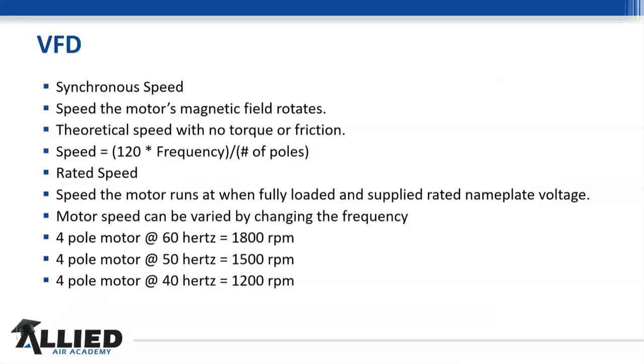It's going to synchronize some speeds. The motor's magnetic field rotates it. You've got theoretical speeds with no torque and friction. All this stuff has to be taken into account. But the last three bullet points here probably become a little bit more important, because as you drop hertz, you're going to drop RPMs. And the reason this becomes important is because a lot of times you'll have two-stage compressors on these units, or two or three compressors on these units. So you're going to need to adjust your indoor airflow to how many compressors and what capacity you're running this unit to. That's why we're getting the better EERs out of these units.